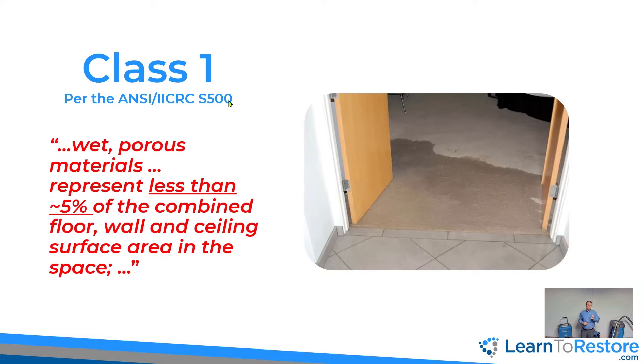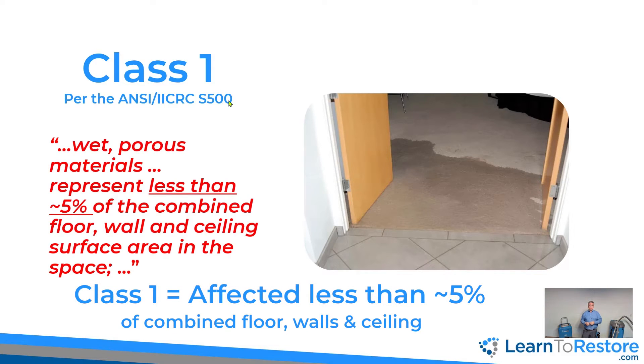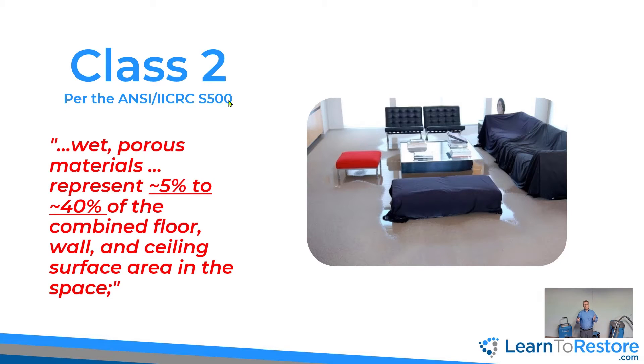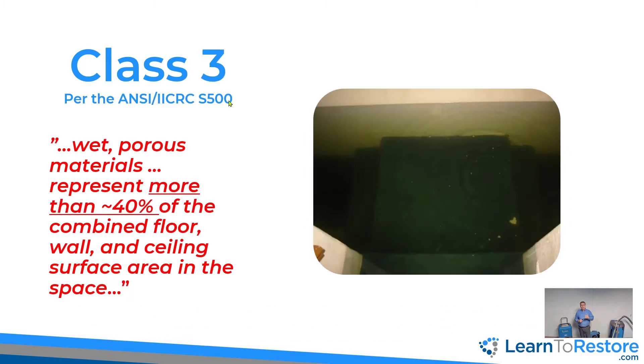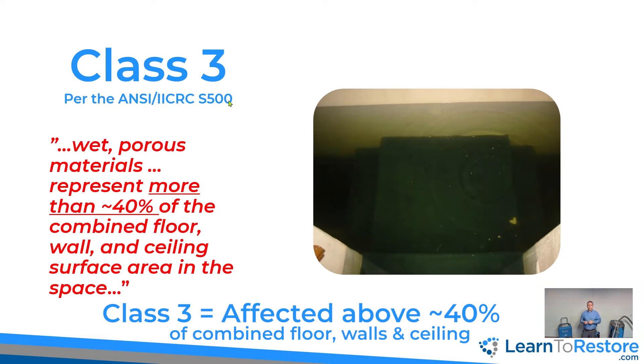We break our classes down into class one, two, three, and four. Class one, two, and three have to do with the percentage of what's wet in my space or my drying chamber. Class four has to do with the type of materials or assemblies that are affected. For class one, if less than about 5% of the total square footage of walls, floors, and ceiling is wet or affected by the water, that would be a class one loss — the least amount of water damage, therefore the least amount of evaporation and dehumidification needed. A class two is between 5 and 40% affected area — therefore more evaporation and more vapor to remove. Anything over 40% would be a class three: the greatest amount of wet affected materials, the greatest amount of evaporation, and the greatest amount of dehumidification needed.